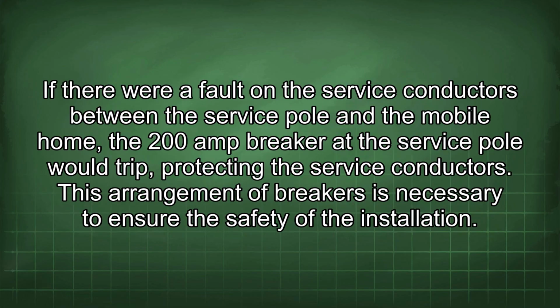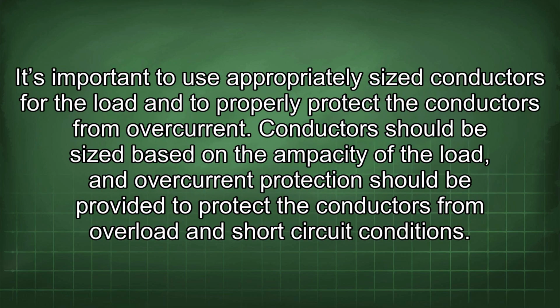If there were a fault on the service conductors between the service pole and the mobile home, the 200 amp breaker at the service pole would trip, protecting the service conductors. This arrangement of breakers is necessary to ensure the safety of the installation. It's important to use appropriately sized conductors for the load and to properly protect the conductors from overcurrent. Conductors should be sized based on the ampacity of the load, and overcurrent protection should be provided to protect the conductors from overload and short-circuit conditions.